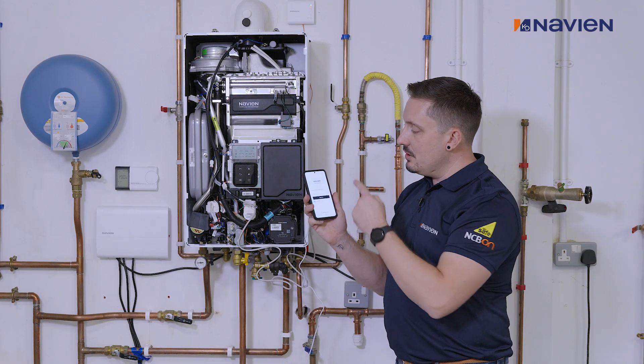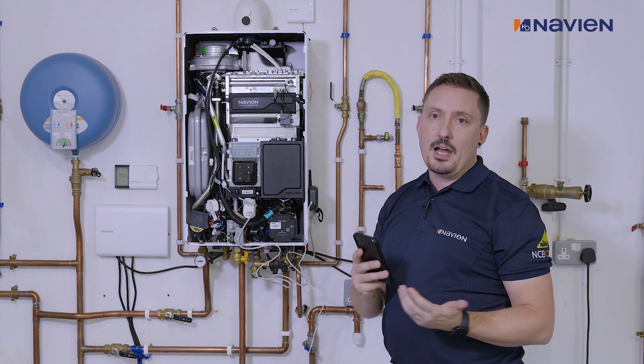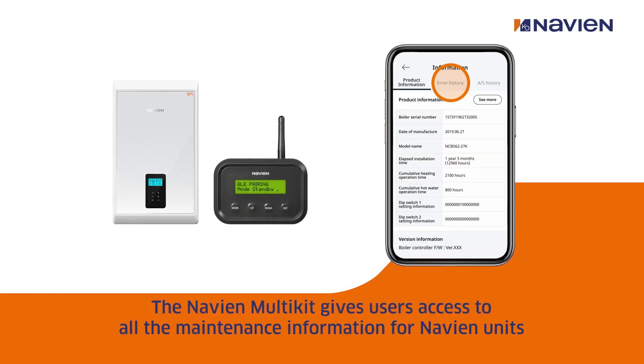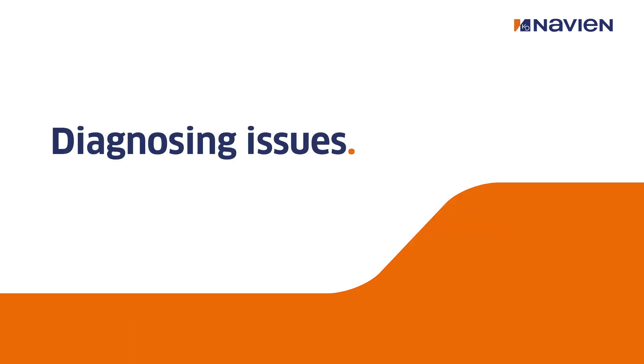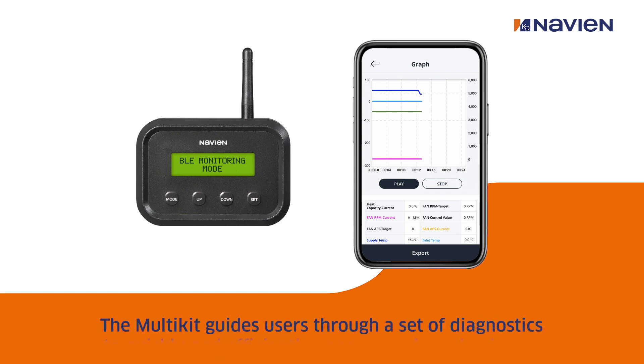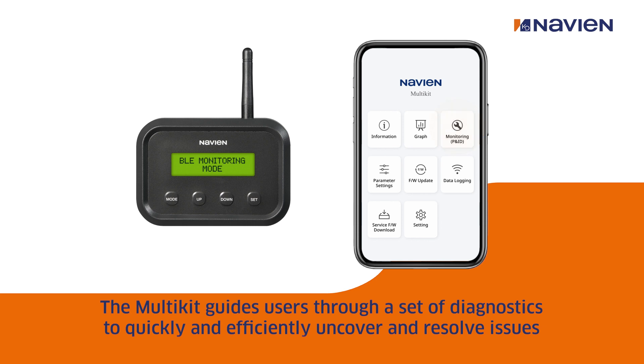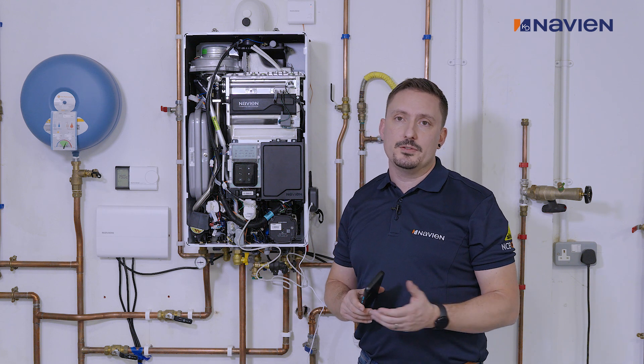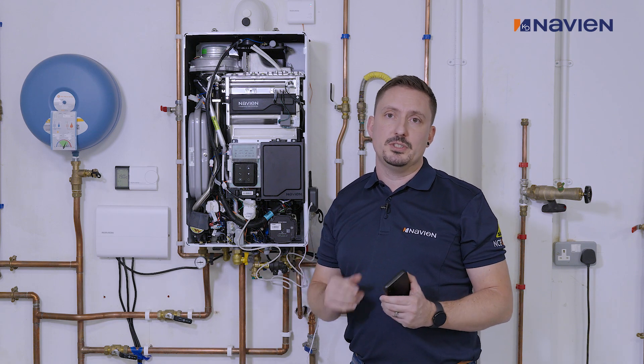Once you've established the connection to the Navien Multikit app, you'll then have the extra features and benefits of the ability to check the operational information from all the sensors within the boiler. You'll also be able to see the diagnosis information such as the flow or return temperatures, flame sensing, signal sensing, fan speeds, pump, mixing valve positions, and more. You'll be able to see those via a graph type or a pictorial type, which is more of an image of a boiler directing you to the points that you're checking.